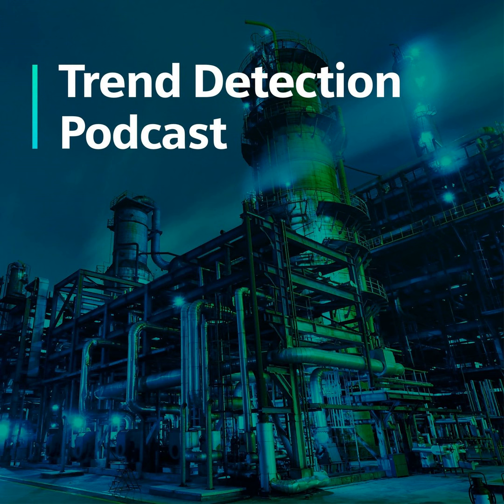From the predictive maintenance side, you could do it by hand if you really wanted to. You could get the data from your sensors, plot it up in your favorite plotting package, or even on a bit of paper, and see where it's going and say, well, actually, that's trending upwards. Looks like in about 2 months it's going to hit some sort of important threshold, or it's getting worse. We don't know why. We should go investigate. You could do it that way.